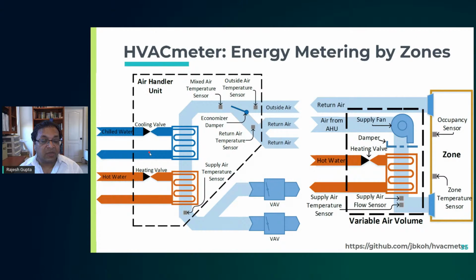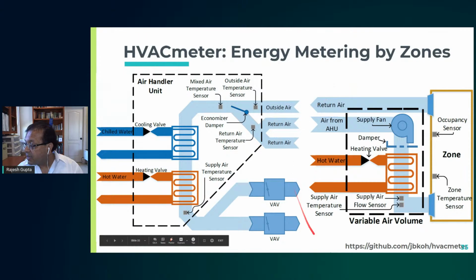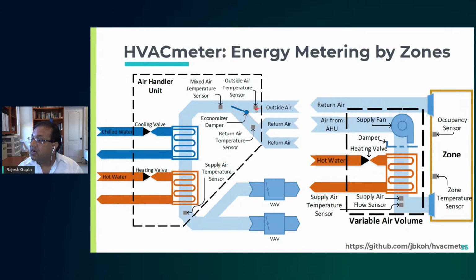So we built a software application called HVAC meter, and what it does is it has an air handling unit that serves multiple VAV units. Each of those has various sensors. For example, it has sensors measuring outside air. It is also mixing air with the return air, and so it has a return air temperature sensor. It has a mixed air temperature sensor. This is called an economizer.